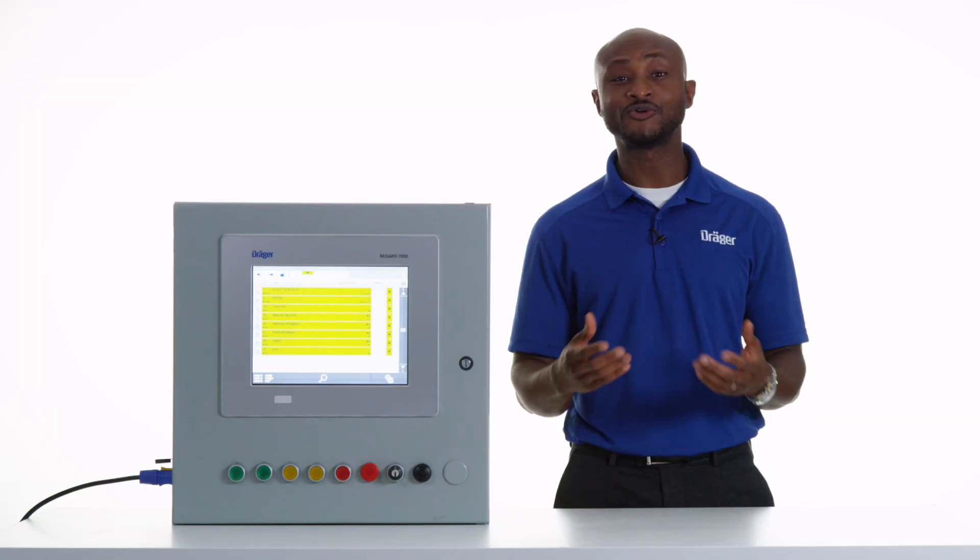The REGARD 7000 can receive and analyze signals from any gas detection device, as long as it has a 4 to 20 mA analog output. This means that it can work with any standard Draeger gas detector, as well as any other competitor devices.